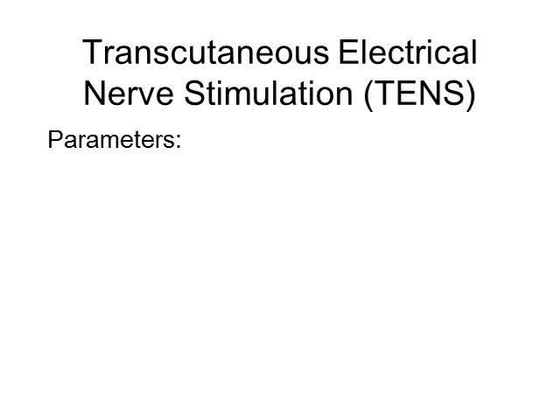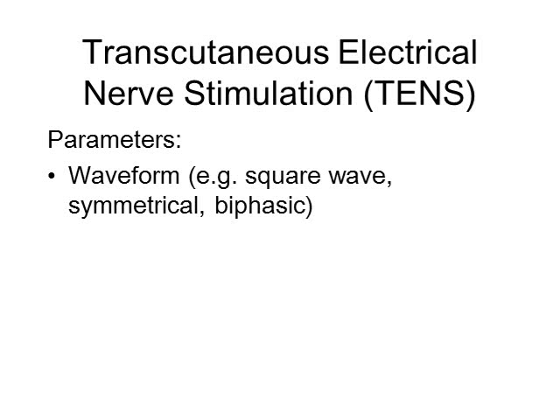Transcutaneous electrical nerve stimulation has a range of different parameters, and it is important that you know about the effects of each. The waveform basically describes the shape of each pulse of electrical stimulation, and will determine the comfort of stimulation. If there is an equal positive and negative charge, then no chemical effects will take place. This parameter is fixed on most TENS devices.